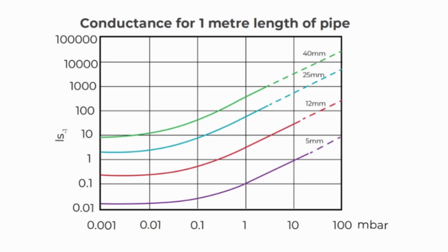Conductance is a measure of volumetric flow divided by pressure drop along the tube or pipe. What this does is allow us to quantify the total effects of viscosity along a tube and geometry into a single value. This value tells you the amount of fluid that will effectively be able to go through your components, which helps drive pump selection. A pump can spin as fast as it wants, but if the conductance is too low, it will be heavily limited by the amount of flow that is able to reach it.